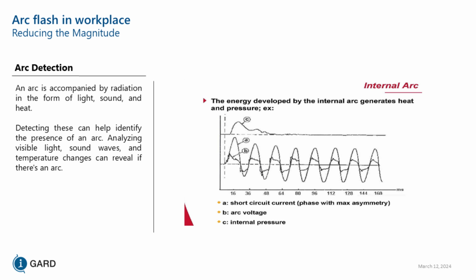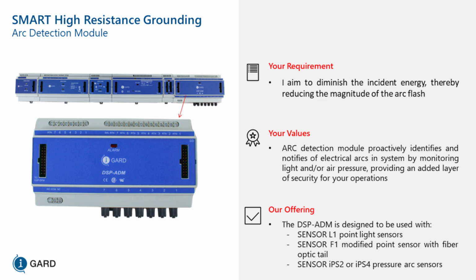We've also developed an interlock, not with current, but with pressure. So this particular module that we designed looks at light and pressure. Now, pressure takes about 10 milliseconds to elevate, so we're looking at isolating the protective device in 95 to 100 milliseconds, which is still faster. And this is the module here. We've got light inputs on the bottom from fiber, light inputs on the top from point sensors, and pressure sensor inputs on the left, top left.